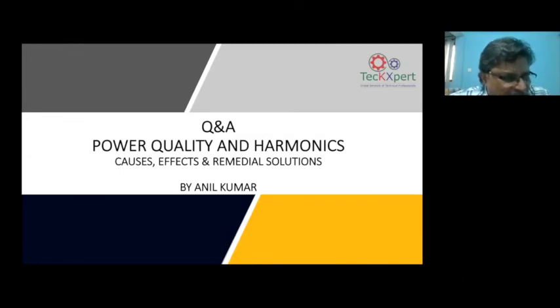Now, here you have two problems. One is the harmonics problem. Second is the electromagnetic interference problem. Because active front-end drives have the IGBTs at the front, these IGBTs are switching at a higher frequency, maybe 16 kHz or 80 kHz, whatever level it is designed for. As the switching frequency of the IGBT is increased, certainly your wave shape will become better, but it will carry a lot of higher electromagnetic interference waves.